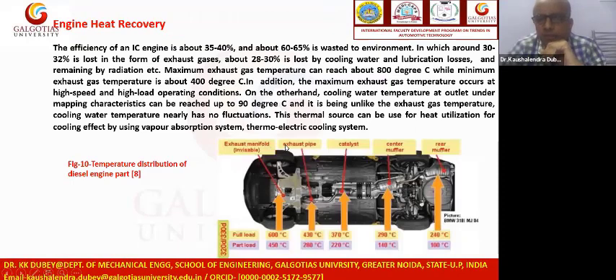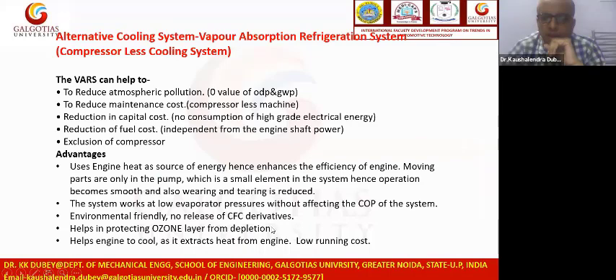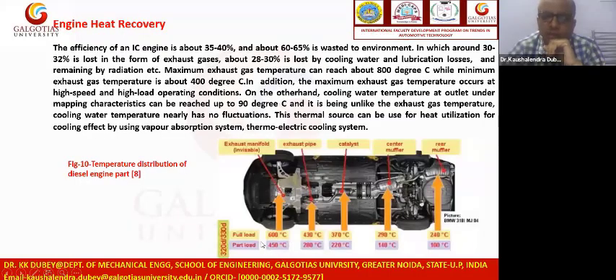Then, through this diagram, we can understand the heat discharge from the different engine parts. At full load and part load, if we run the engine, different temperature ranges are available from the engine emission. So here we have the opportunity for engine heat recovery from the exhaust manifold, and we can see that when the engine is at part load, the available temperature is about 400 degrees C and at full load about 600 degrees C. That means we have very good, tremendous potential for heat for cooling generation by using something other than the VCR system. So the engine is actually treated here as a thermal source, as an energy source.